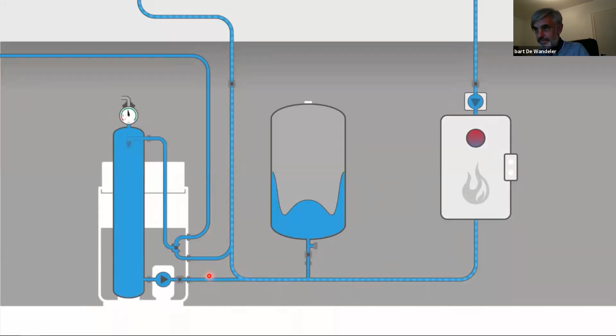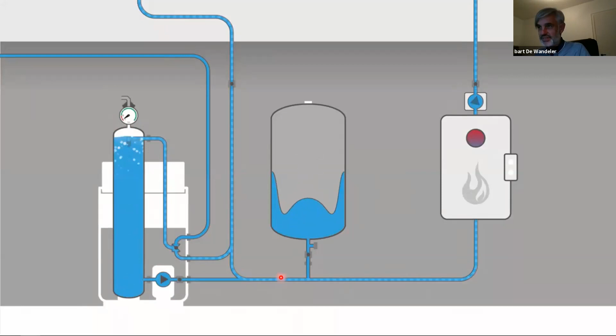So what we are going to do is start the degasser. The pump is running, we are going to negative pressure. This is air-relieved water, and we pump it up into the system. This happens very fast, one cycle, and here we have the pressure again.